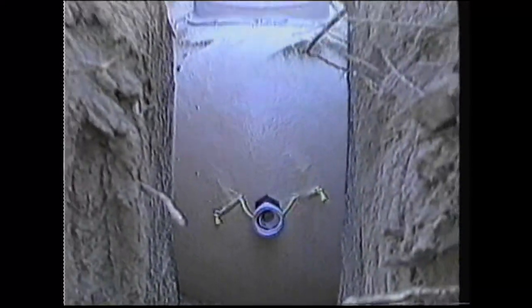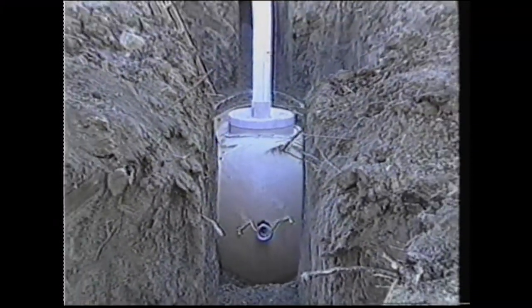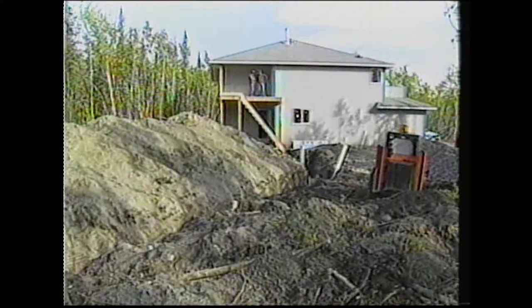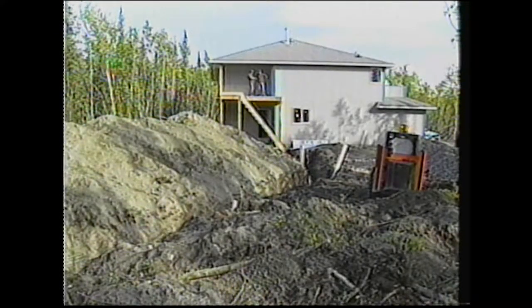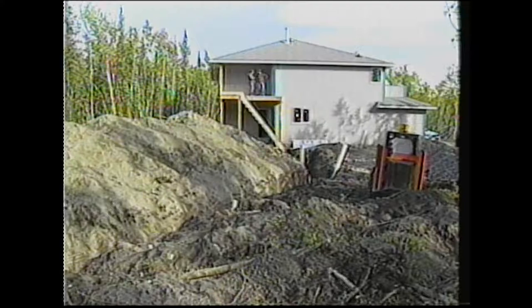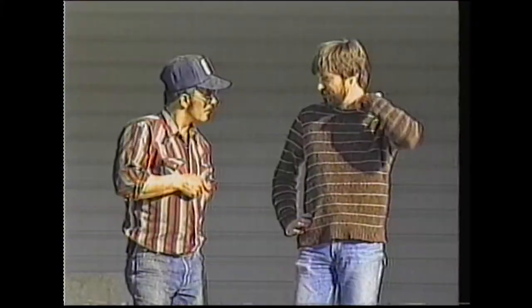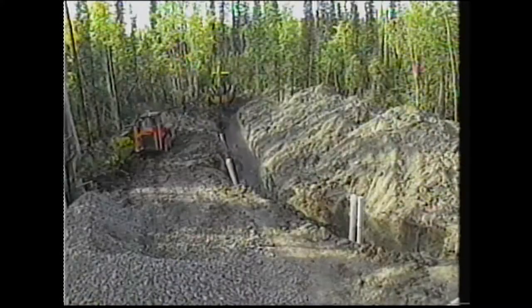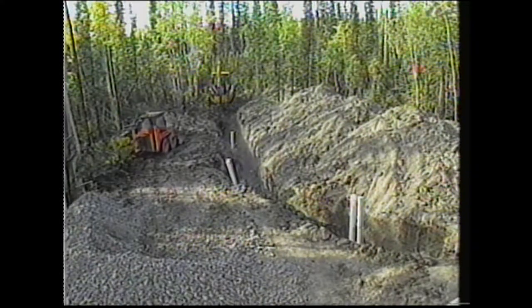Liquid effluent from the settling chamber flows from the siphon compartment and is discharged to the soil absorption system in large flushes. The siphon process helps prevent freezing and allows the even distribution of the effluent throughout the system. This also reduces the chance of failure due to clogging and overloading. There is a misconception by many that the field is the only part of a system where sewage is treated. In fact, it's a two-part treatment process involving both the tank and the field. Each must be working properly to effectively treat the sewage.